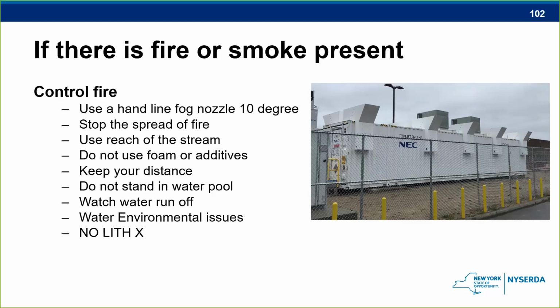Keeping your distance. If there is some sort of water collection, we want to make sure that the firefighters do not stand in that water pool, because of the potential, again, of electrical leakage coming back to them. Watch the runoff. If this container that we see again is on the rooftop and you have some way of introducing water, or there's an automatic sprinkler, we got to make sure that the water doesn't collect in here, because now you're just putting extra weight on the rooftop itself. So we got to make sure there's some sort of runoff there. For those people that are looking at the plans for this stuff, ask them that question: how does the water get out of there if we're on a rooftop? We don't want that water collecting inside the cabinet itself.